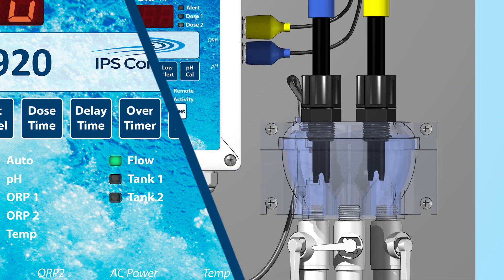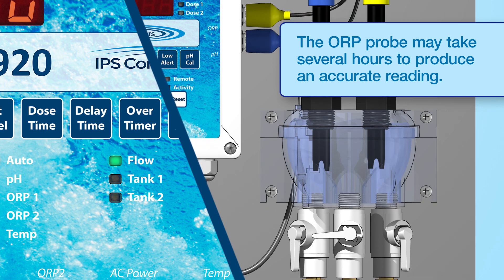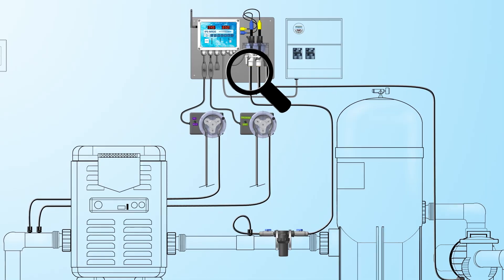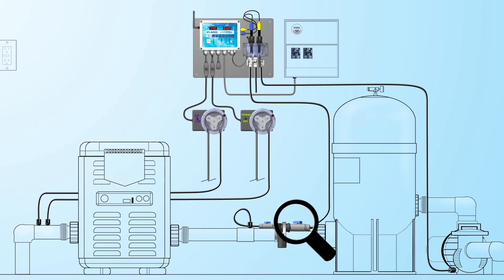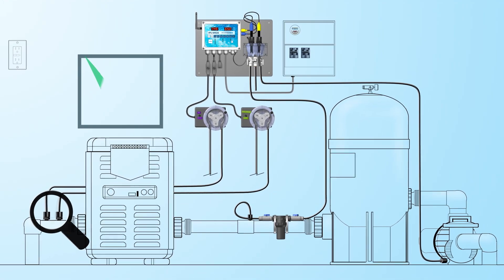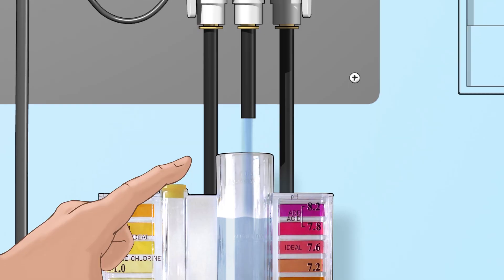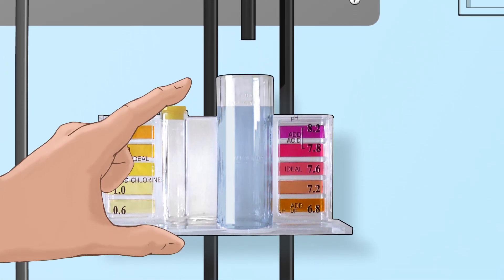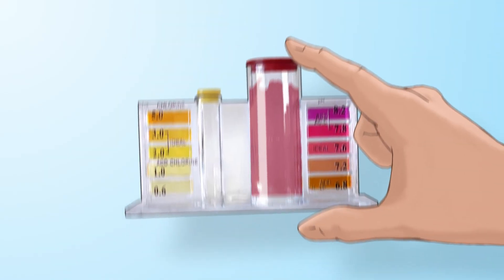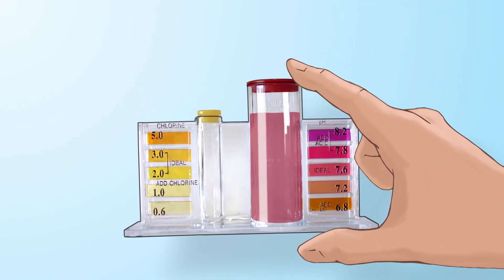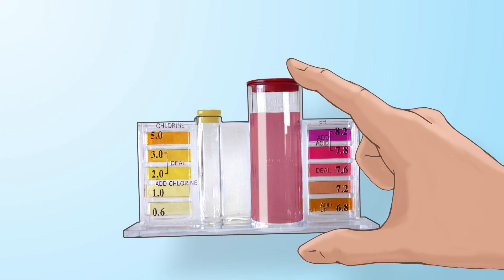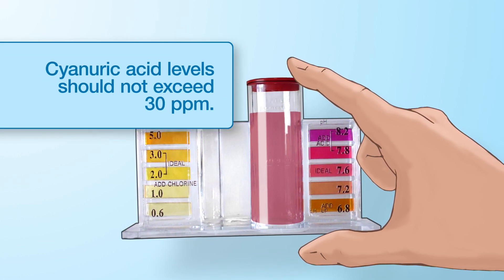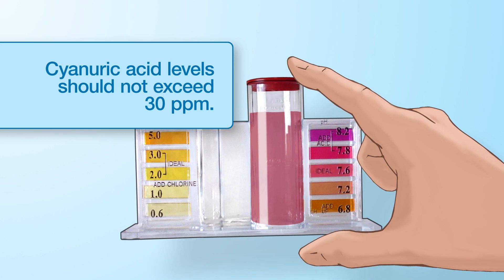Water should pass over the pH and ORP sensors to allow for accurate readings from the pool or spa. Make sure there are no leaks in the system. Using a DPD test kit, open the valve on the center port and test the water. Manually adjust the water in the pool to the desired pH and sanitizer levels. For best results, the cyanuric acid levels should not exceed 30 parts per million.